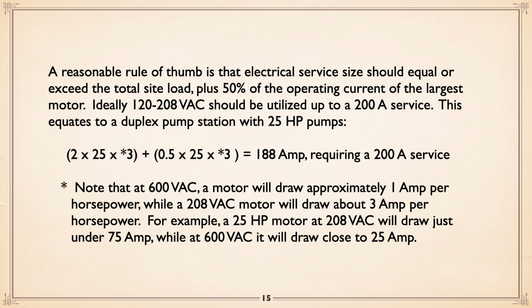Now, if we take a look at the example I've given here, 25 horse. So you've got two 25 horse motors, and because 208, or 200, sometimes used as 200, is roughly 3 times, okay? So 2 times 25, that's the base load. But we also need to add 50% of the largest motor, which in this case is half of 25 times 3. All that adds up to 188 amp. So we tell Hydro we want a 200 amp service, okay? And away we go.